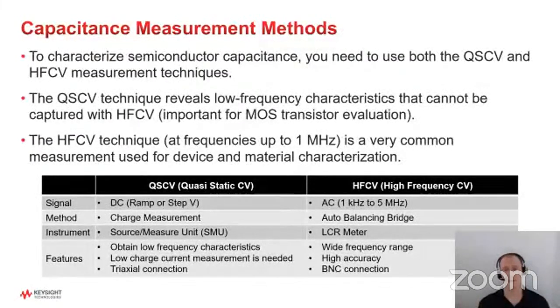The high frequency CV measurement, again, typically we usually do that around megahertz, uses an LCR meter with an auto balancing bridge, and it uses BNC connectors. And so there's some things you have to keep in mind as you're doing those high frequency measurements in terms of compensation and things like that as well. So I'll cover in the following slides some of the more details about both of these techniques. I'm going to start off first talking about quasi-static CV measurements.